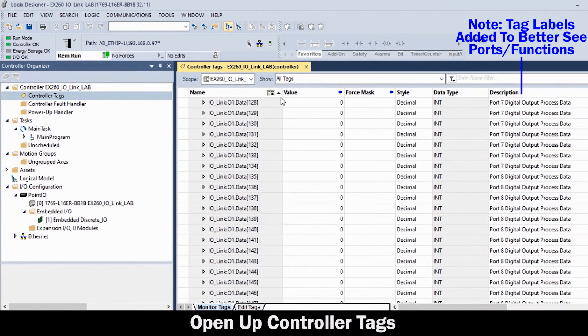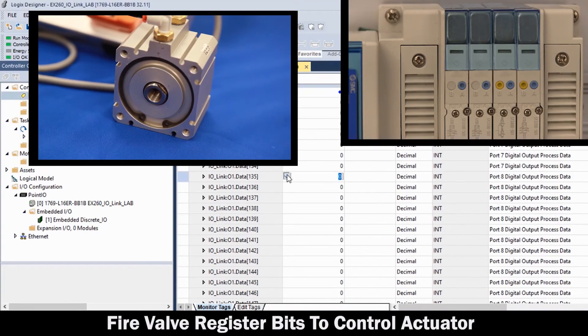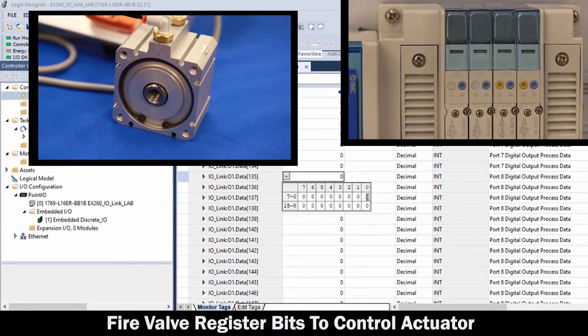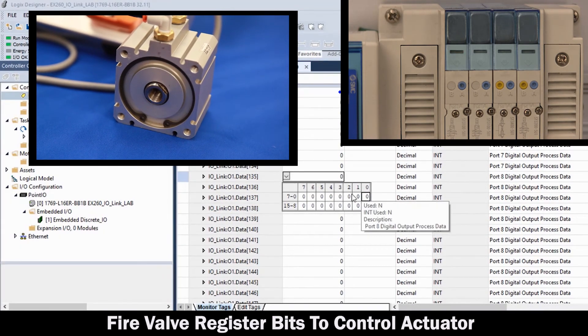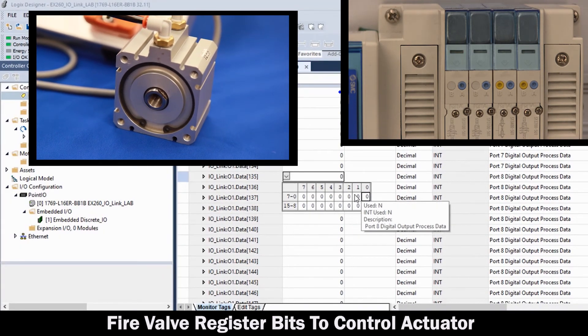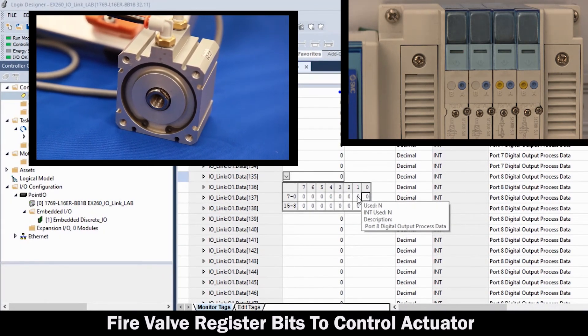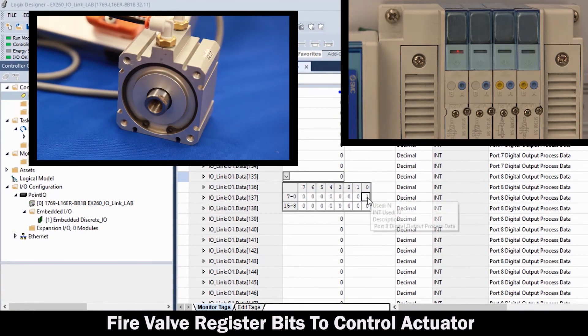Note the tag device descriptions that were added as helpful labels for the IO-Link Master port functions. Now, actuate the valve by firing the EX-260 solenoid bits from the register. And now we can see that the actuator is running from the valve through IO-Link and the EX-260.